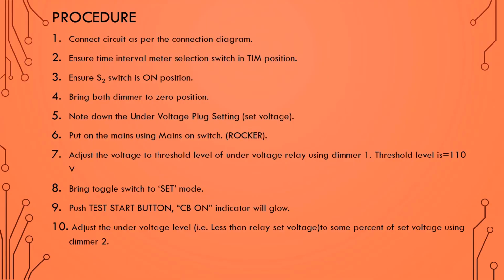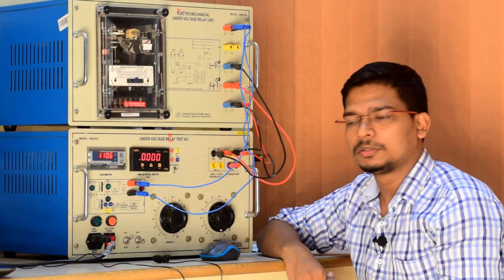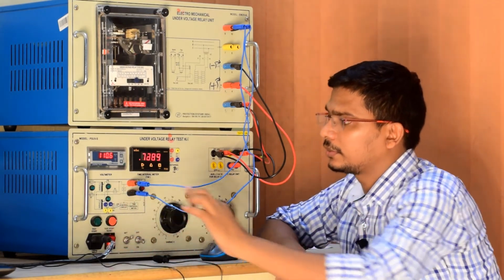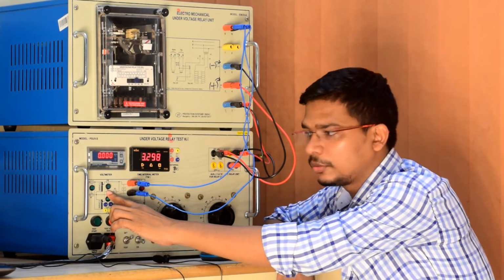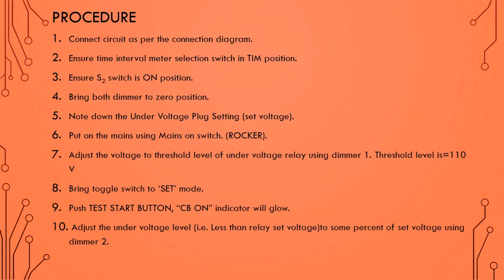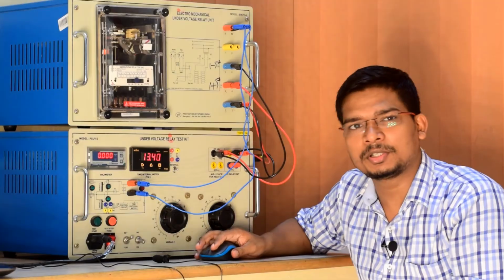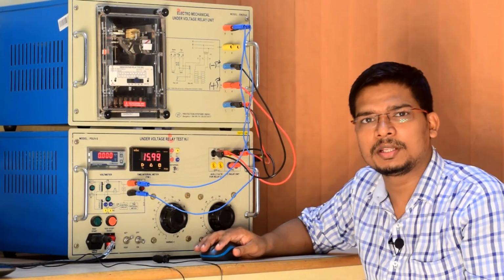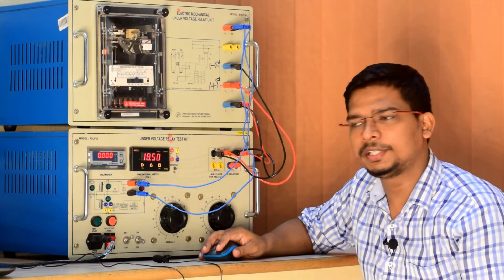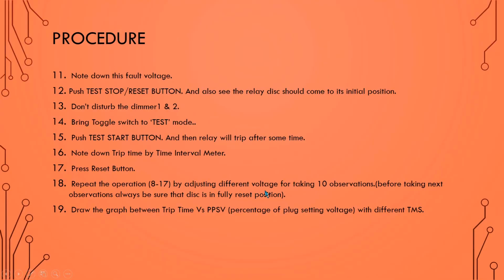Then push test start button, CB on indicator will glow. So now we will push test start button. So CB on indicator will glow. So this is glowing actually. Then adjust the under voltage level to some percentage of set voltage using dimmer 2. That percentage of set voltage, as already given in the observation table, accordingly we will take the observation. Then note down this fault voltage. Then push test stop button.